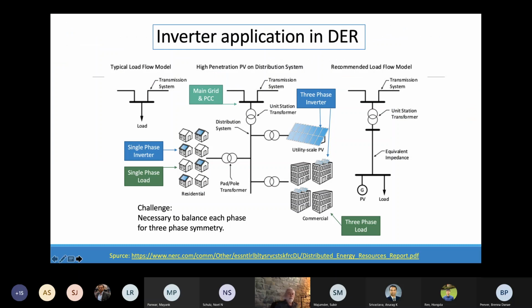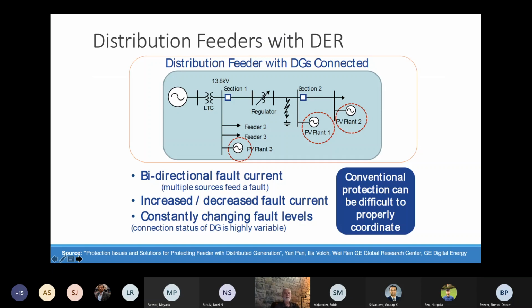Inverter application, inverters who are driving these solar photovoltaic systems can be single phase, three phase, can be on the roofs of the houses, or utility scale PV, which is now beginning to proliferate to a bigger extent. And all of those things could be part of the new distribution, even more medium voltage level for interconnection or utility scale systems. But generally, distribution is what we are talking about and what will be the subject of our talk. So what happens with protection when we are talking about it?